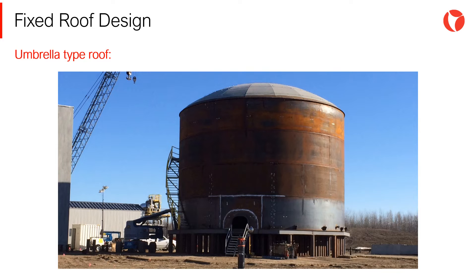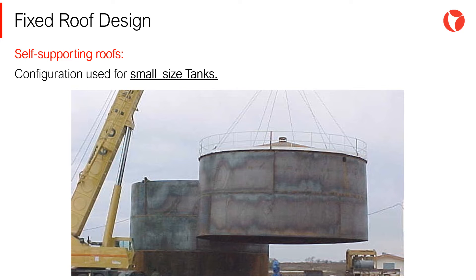On the circumferential axis, the umbrella type roof is similar to the cone type roof. Self-supporting roofs consist of a set of overlapped or butt-welded plates. Because of their physical shape, they are capable of supporting themselves without any structural element, and are supported at the outer part of the roof by the tank shell. The thickness of the roof plates must be calculated and designed so that the roof can be self-supported.